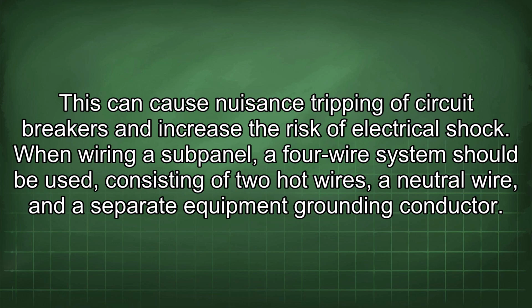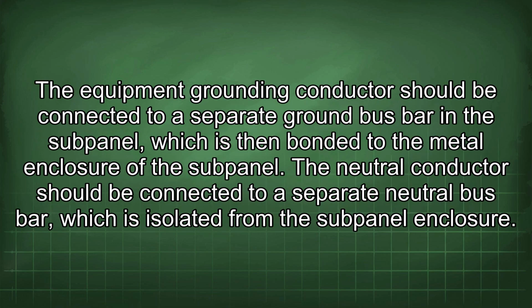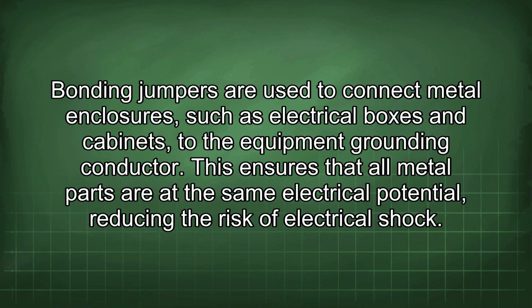When wiring a subpanel, a 4-wire system should be used, consisting of 2 hot wires, a neutral wire, and a separate equipment grounding conductor. The equipment grounding conductor should be connected to a separate ground bus bar in the subpanel, which is then bonded to the metal enclosure of the subpanel. The neutral conductor should be connected to a separate neutral bus bar, which is isolated from the subpanel enclosure. Bonding jumpers are used to connect metal enclosures, such as electrical boxes and cabinets, to the equipment grounding conductor.